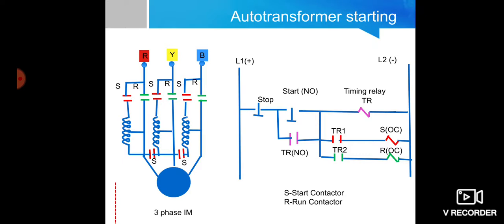So after a certain span of time, what will happen? So this is the direction for initially when the auto transformer was connected to have a reduced voltage across the circuit. Then the induction motor operates. Now the second phase, that is the running phase of this induction motor. Let us see what will happen, because of which this TR2 is going to get closed and ROC will get energized, because of which the contactors related to ROC are now getting closed, and this would be the direction of current.